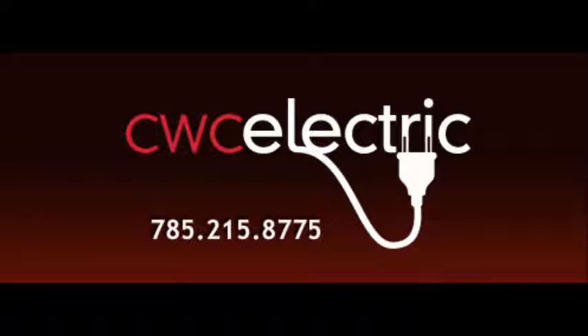Now, moving on past that, let's say you've got an acceptable panel, but you talked about double taps. What you mean by that is people have terminated several wires on a single circuit breaker. Now, there are a couple brands of circuit breakers that allow that. They're actually rated to have 2 wires. And so sometimes an inspector will automatically look at that as double tapped and it doesn't pass inspection. But if we look at the actual brand, and it's rated for it, it's okay. But if it's not, that's a simple fix to take care of.